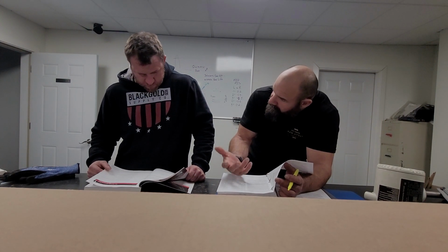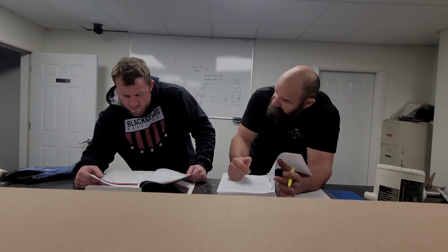Chapters 1 through blank of the NEC apply generally unless they are modified by the later chapters. So it's the first 4 chapters. The first 4 chapters are general, like general requirements for wiring, the neutral conductor. They call it the grounded conductor in the code, and it shows you all that stuff. After that, it's special occupancies, special conditions and special equipment. Those are chapters 5, 6, and 7. Chapter 8 is independent, communications equipment and stuff. And then chapter 9 is just a bunch of tables.